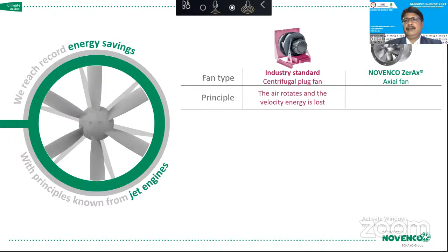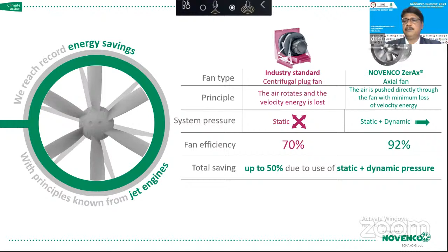If you consider any plug fan along with our fan, in our fan you can use static as well as dynamic pressure, whereas in a plug fan you can use only static pressure. Fan efficiency in the highest plug fan is 70%, however in normal operating conditions you are not going to achieve more than 60 to 65%. In our case, the highest fan efficiency is 92%, and you can get an average of 88% to 90%. So total saving is up to 50% by using static and dynamic pressure.